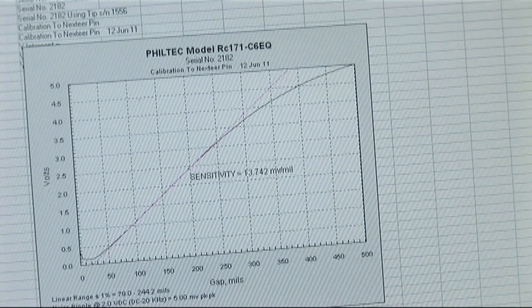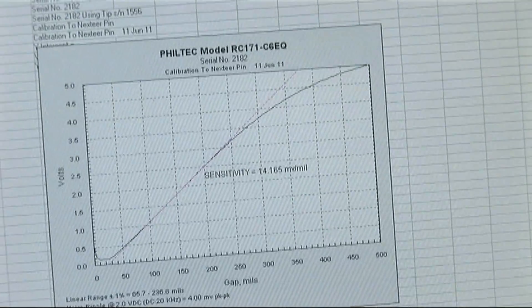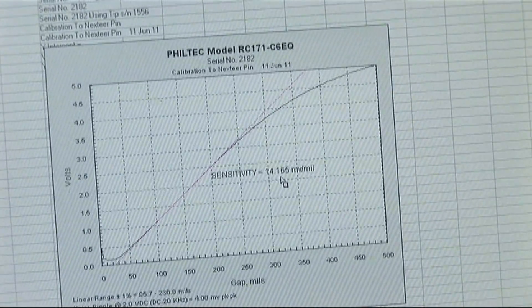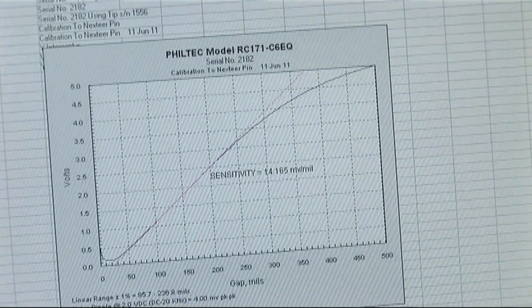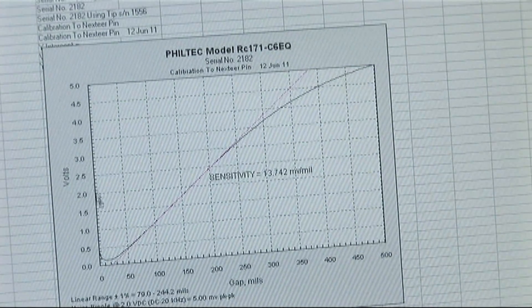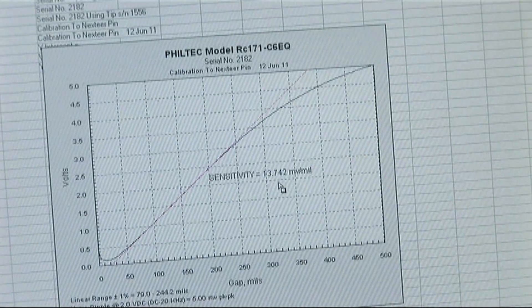All right. And once more, if we look at yesterday's calibration, sensitivity is 14.165 millivolts per mil. And if we paste in the calibration that we just did today, you could see a slight change, a little drop in sensitivity, 13.72.